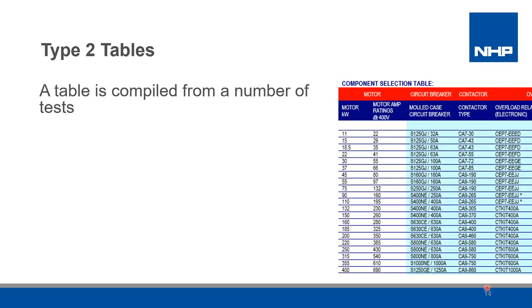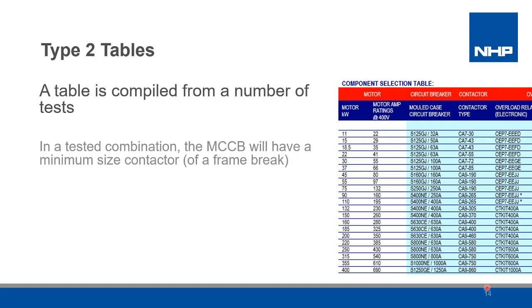A Type 2 table is compiled from a number of tests. Not every kilowatt rating is required to be tested, but they are compiled around frame breaks of the circuit breaker and contactors for a table which is in accordance with the standards. So normally you would test the circuit breaker with a higher trip rating with the smallest compatible contactor, and this may cover a number of starter ratings.